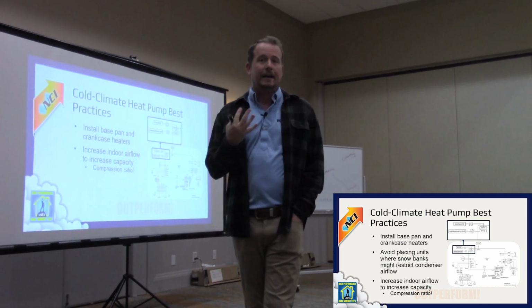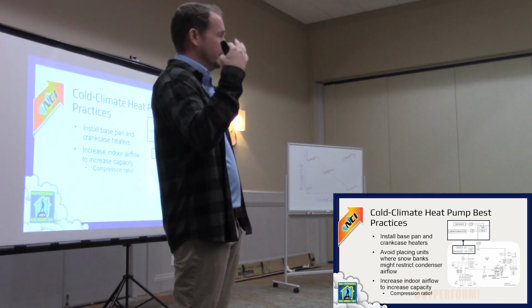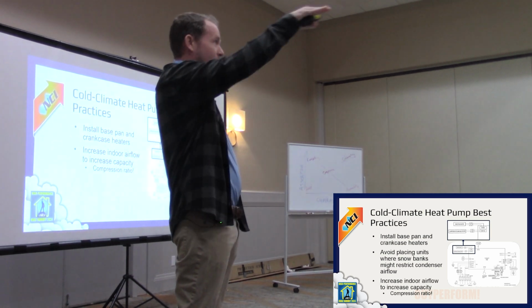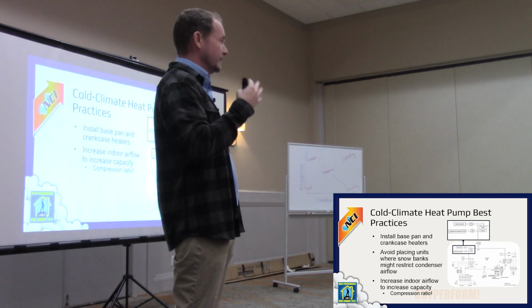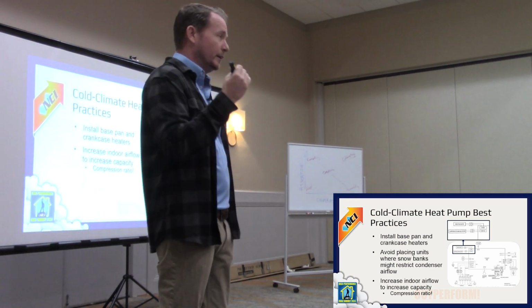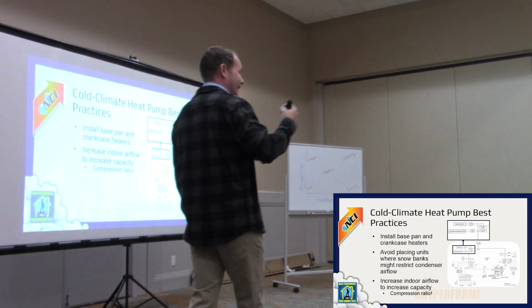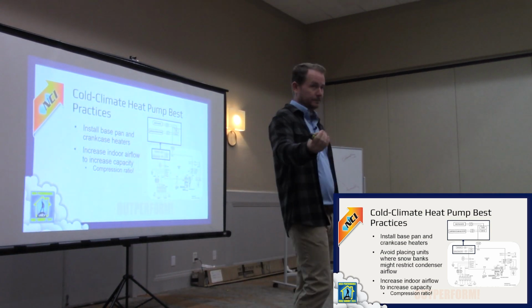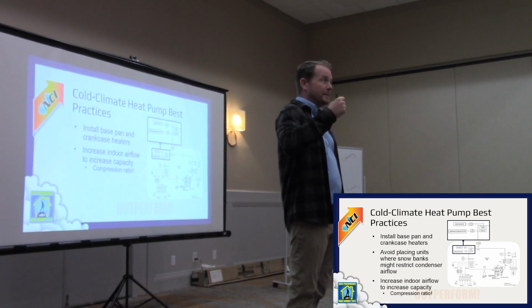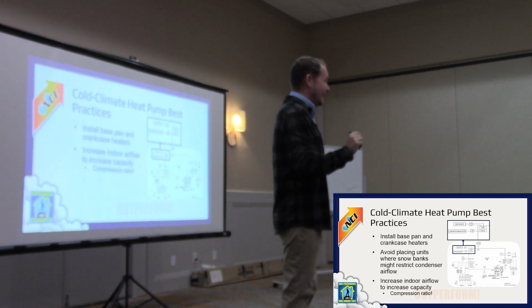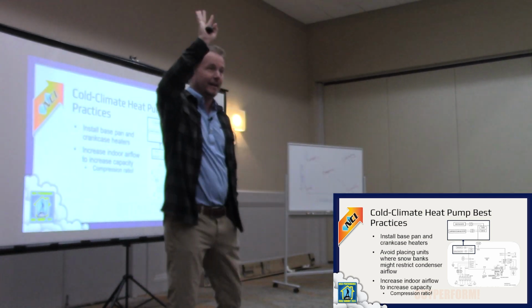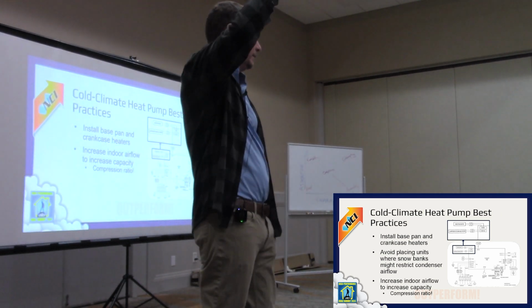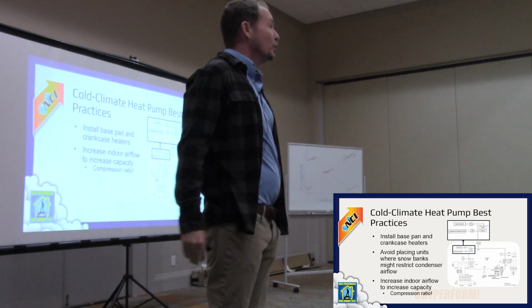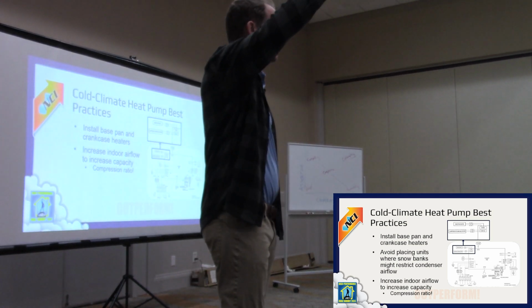If you select your diffusers better, design your duct system better, direct it across the ceiling where possible, and you're not blowing air on people, then you can get away with running higher airflow over your indoor coil. When you do that, you get better capacity and efficiency. In a real way, when people feel that air they think, oh that's cold, we need to warm that up. Then you slow the air down over the coil and it feels warm.